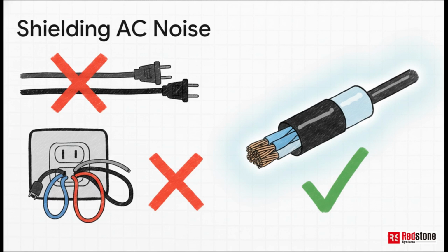The rules are super strict. Never run your telephone lines parallel to AC power supplies, computer lines, or other data cables. And definitely never share the same power socket. Now, if you're in a bind and absolutely must run lines near potential interference sources, you have to insulate them. The manufacturer highly recommends using shielded twisted pair, or STP cables, or utilizing conductive adhesive tape to physically block that interference from reaching your voice data.